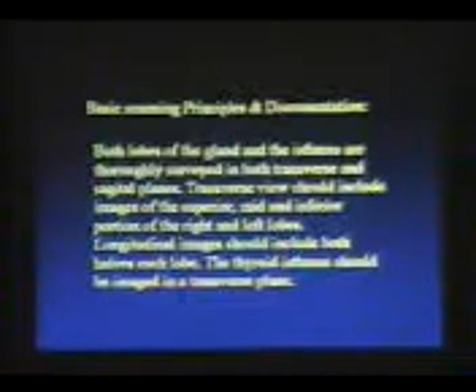A high frequency transducer is used because we don't need the penetration and we need good resolution, and for that purpose we usually use a transducer with frequency from 6 to 10 megahertz. Although transducers are available up to 13 megahertz, and in cases where the thyroid gland is small or the patient is thin and lean, we can opt for higher frequencies. Conversely, if we have a patient with a big neck or who is very obese, we will need to go to the lower frequency range and we will use a transducer with a frequency of 5 MHz.